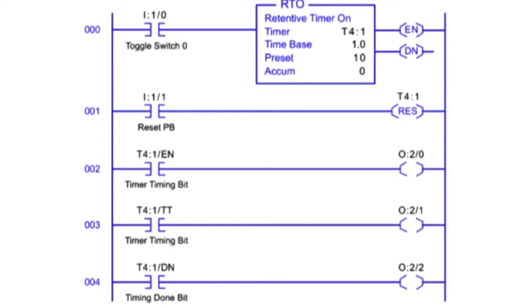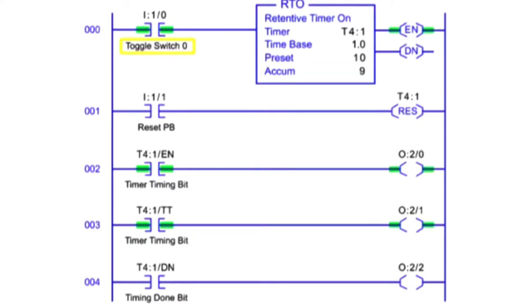The Retentive Timer On is enabled and begins timing when the input conditions are true. By changing the input condition to false in the Retentive Timer circuit, the accumulated value stops timing and retains the time recorded until the input condition goes true again. As the accumulated value reaches the preset value, the Done bit goes true and enables the output. A programmed reset instruction with the same address as the timer is used to reset the Retentive Timer's accumulated value.